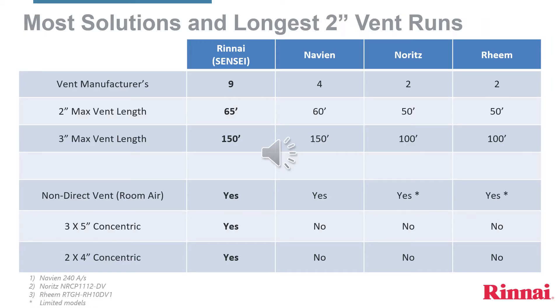Rinnai Sensei will offer the most venting solutions and the longest 2-inch PVC 636 vent runs. In the 2-inch, we have a maximum of 65 equivalent feet. With equivalent, we mean that the addition of a 90-degree elbow adds 5 feet to the total, and a 45-degree elbow adds 2.5 feet. If longer than 65 equivalent feet, then you would need to use 3-inch from the heater to a maximum of 150 equivalent feet.